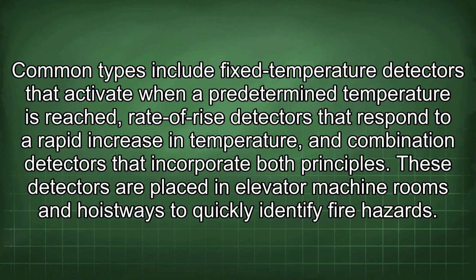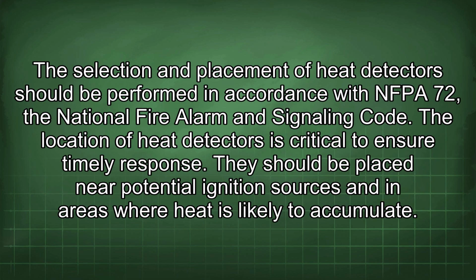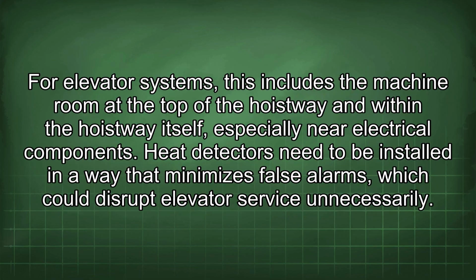These detectors are placed in elevator machine rooms and hoistways to quickly identify fire hazards. The selection and placement of heat detectors should be performed in accordance with NFPA 72, the National Fire Alarm and Signaling Code. The location of heat detectors is critical to ensure timely response. They should be placed near potential ignition sources and in areas where heat is likely to accumulate.